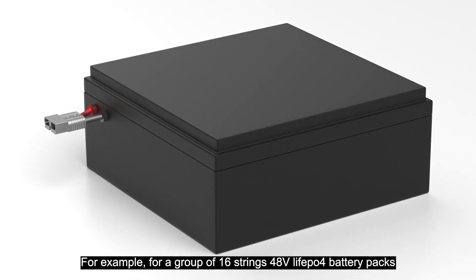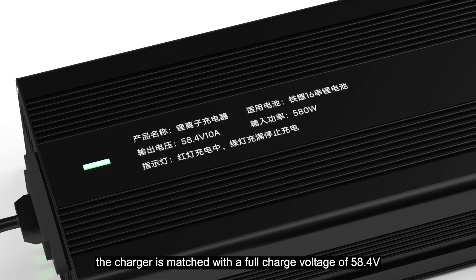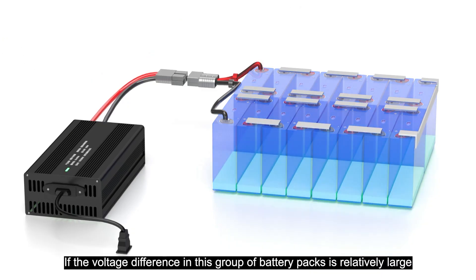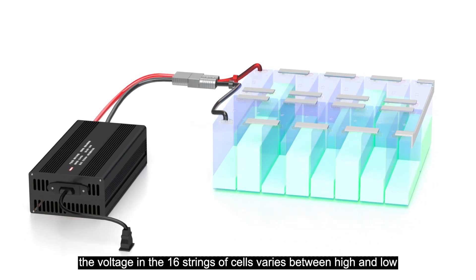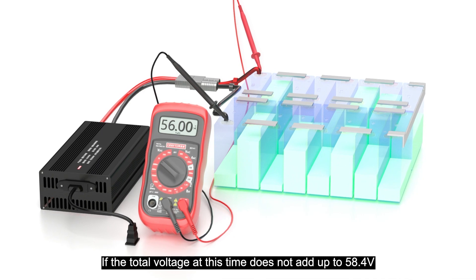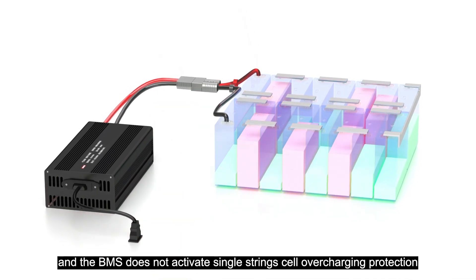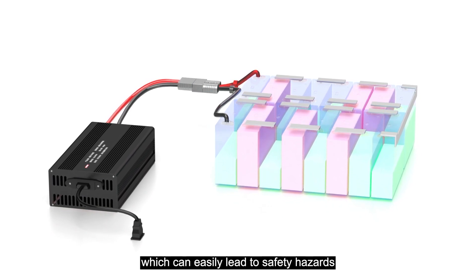For example, for a group of 16-strand 48V LiFePO4 battery packs, the charger is matched with a full charge voltage of 58.4V. If the voltage difference in this group of battery packs is relatively large during charging, and the voltage across the 16 strands varies between high and low, if the total voltage does not add up to 58.4V, the BMS does not activate single-strand cell overcharge protection. So a single battery cell that has already reached full charge is still being charged, which can easily lead to safety hazards.